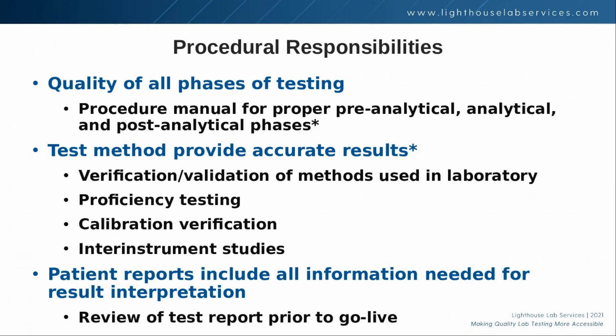The lab director will also need to check that the patient report includes all pertinent information a physician would need to interpret the results provided. This can include reference ranges, or for qualitative testing you will often see cutoffs for positivity. Typically, this is performed by review of a finalized test report prior to the lab going live with testing.